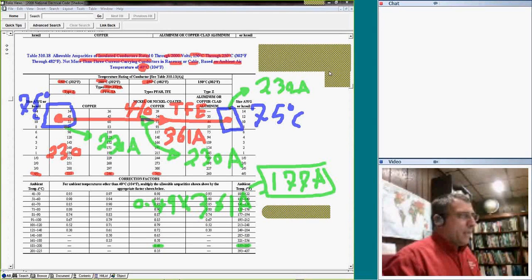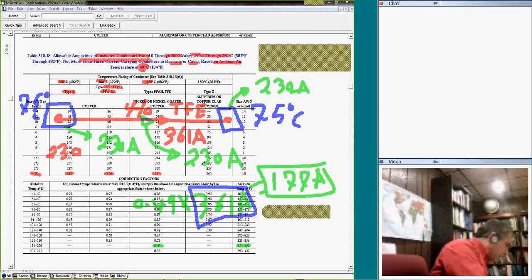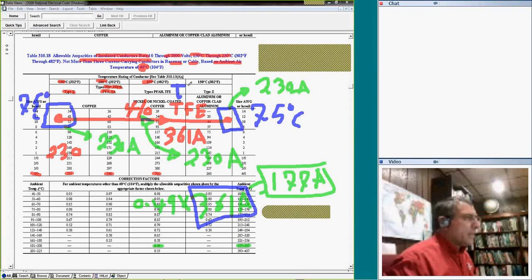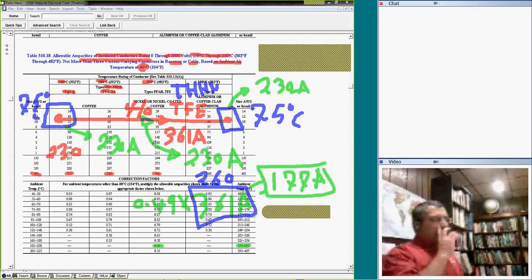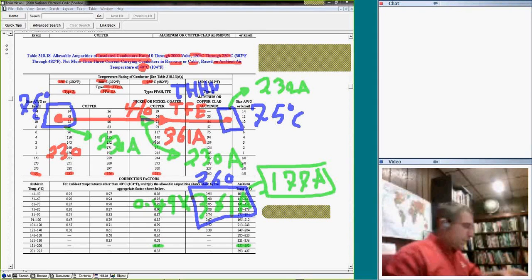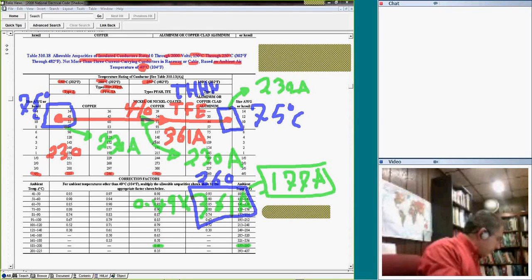What that means is this gives you a higher amp value to start the rating from. Can you see that? Otherwise, I would have to use a smaller amp value. If it's not this insulation, say it had been THHN, you have to start with 260. So starting with 260 and ending up with a very small amount of amps, for the same temperature, the factor doesn't even get that high, it's 0.41 times 260.